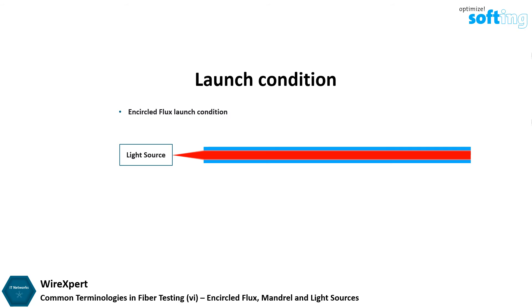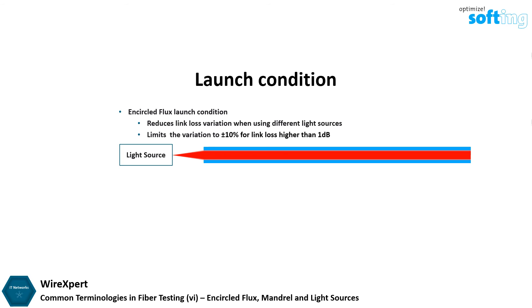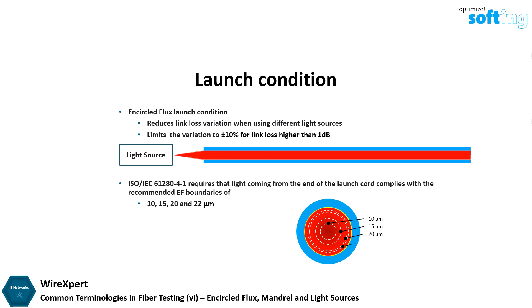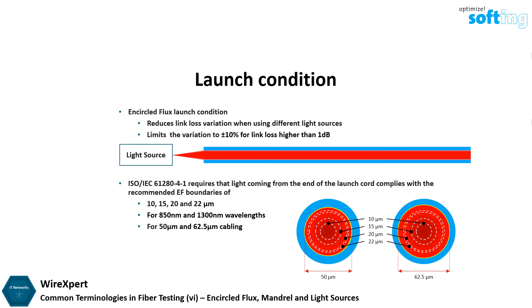An encircled flux launch condition reduces link loss variation when using different light sources, limiting the variation to plus or minus 10% for link loss higher than 1 dB. The ISO IEC 61280-4-1 requires that light coming from the end of the launch cord complies with the recommended EF boundaries of 10, 15, 20, and 22 microns for 850 nm and 1300 nm wavelengths, for both 50 micron and 62.5 micron cabling.